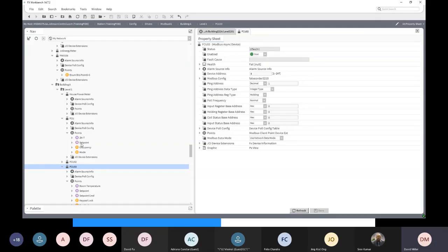In Metasys, you have to go out into a separate application, which you might not even have, and create the VND file and do all that problem solving in the VND file, then take it to site, put it in, and it'll either work, which means you got everything right, or something will be wrong, in which case you have to go back, work out what you did wrong, make the changes, send it back out, try again. So this is a much more flexible, quicker way to do it.